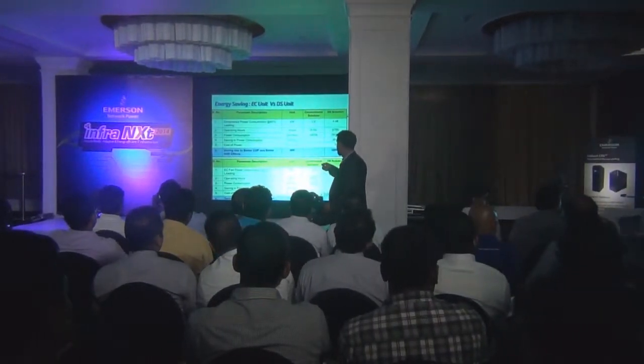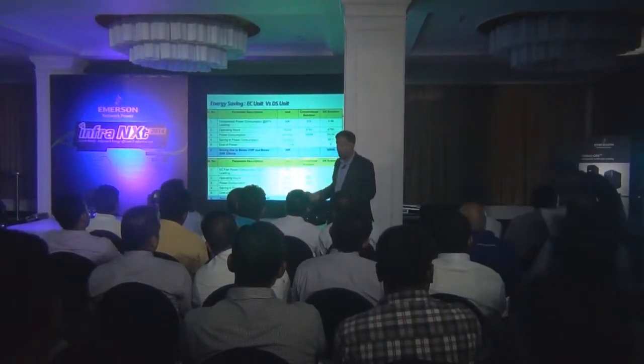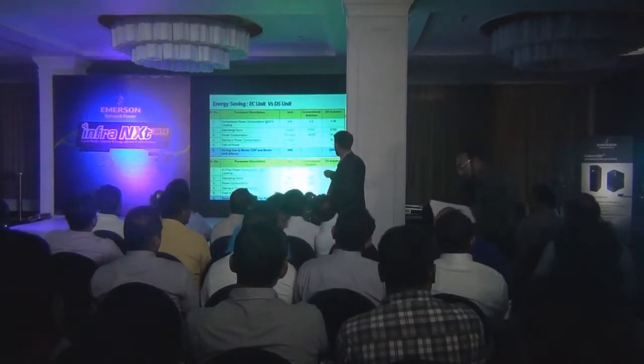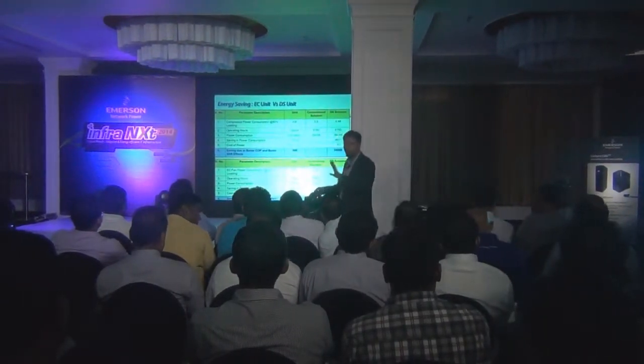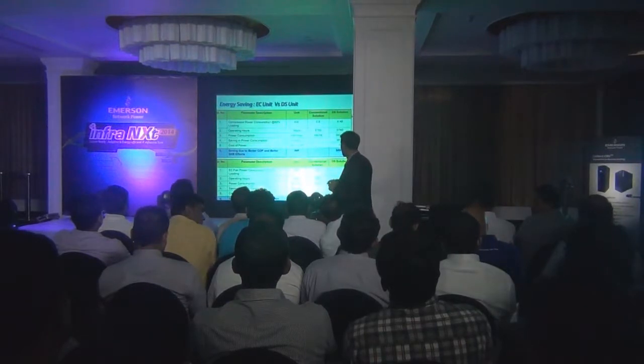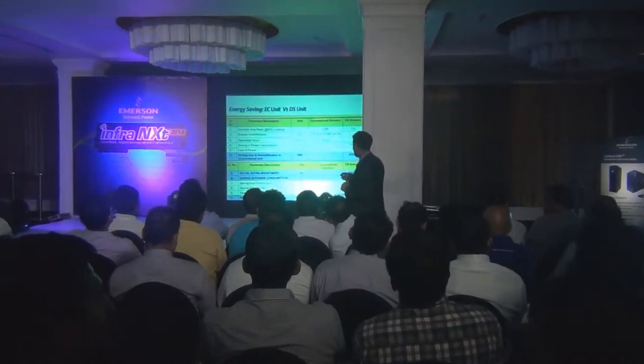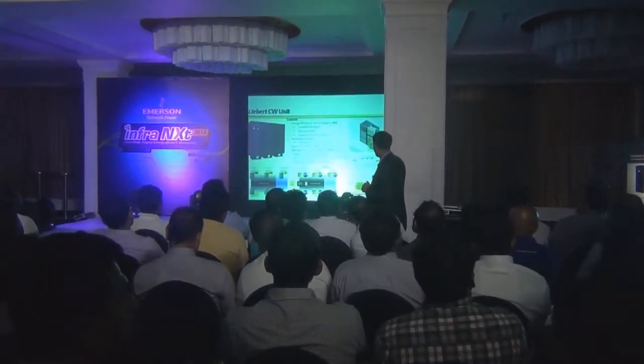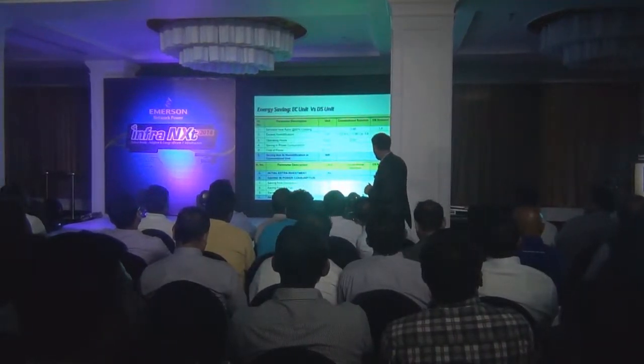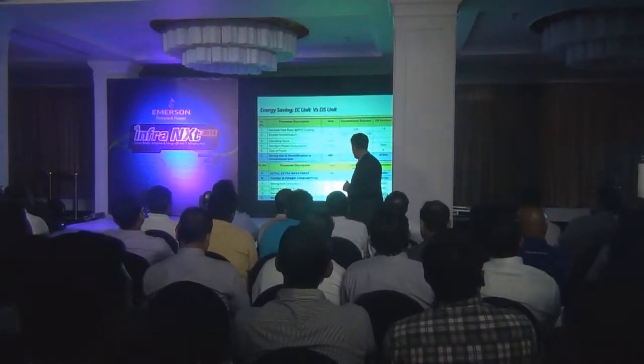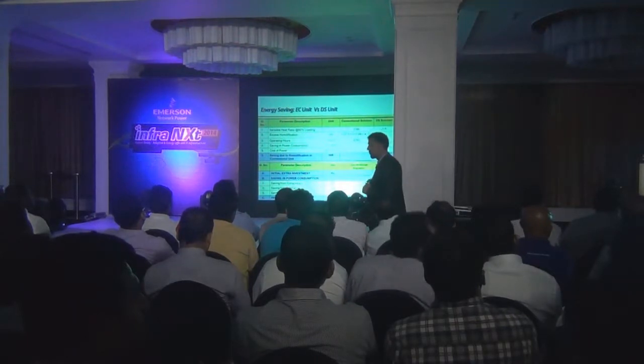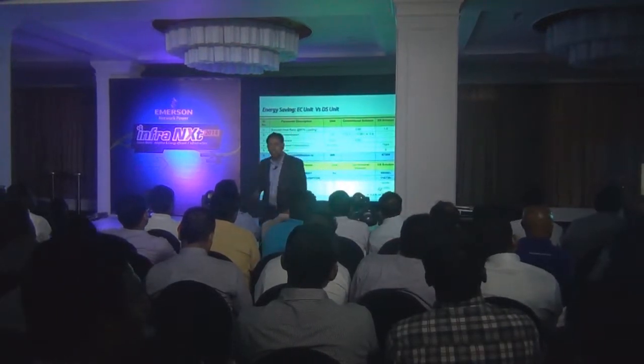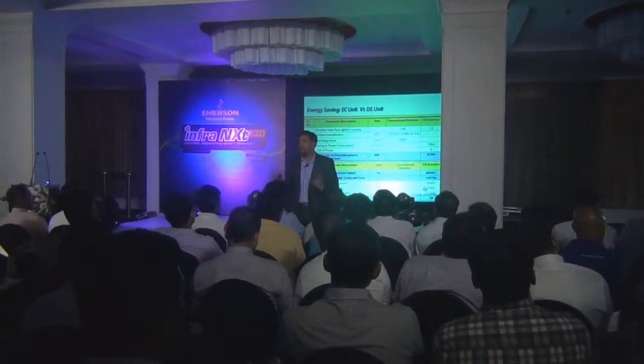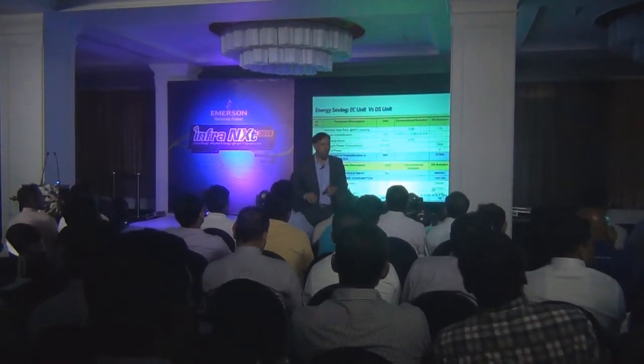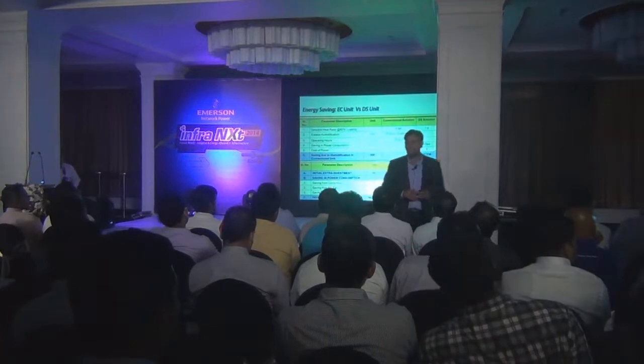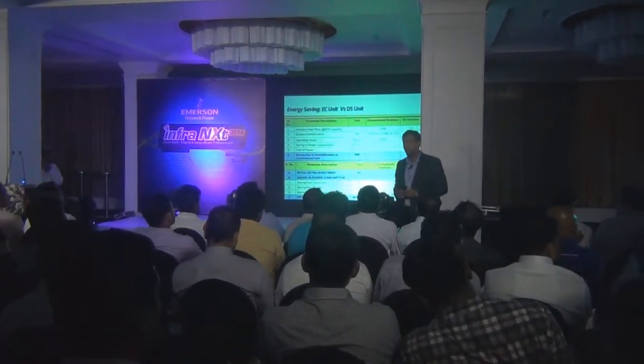What is the power consumption difference between an EC fan unit with fixed scroll and the digital scroll unit? This is on the compressor side, you save this much yearly just for a 5 TR machine, we did the comparison. And on the EC fan you are saving this much. And on the humidification on the EC to digital you save this much. Overall, the ROI you can see at the bottom, it's 10 months. So what you invest today for digital scroll, the ROI is 10 months. I'm sure you will love to have such a system which has less than 1 year ROI.